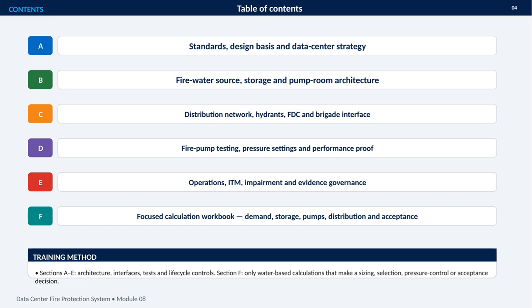From there, Section C follows the distribution network, including hydrants, the fire department connection, and the interface with the responding brigade. Section D addresses fire pump testing, pressure settings, and performance verification. Section E shifts to the lifecycle: operations, inspection, testing, maintenance, impairment management, and evidence governance. Finally, Section F is a focused calculation workbook. It covers only water-based calculations that support decisions about demand, storage, pumps, distribution, sizing, pressure control, and acceptance.